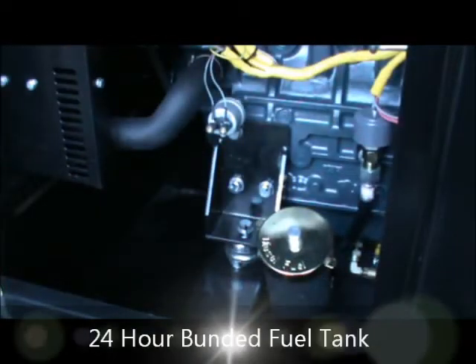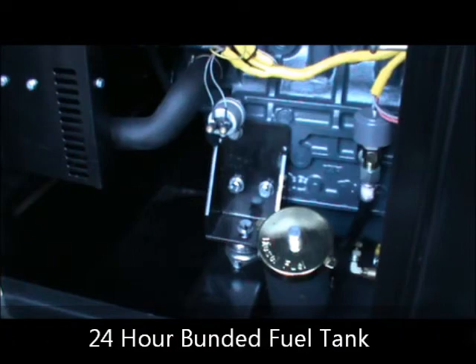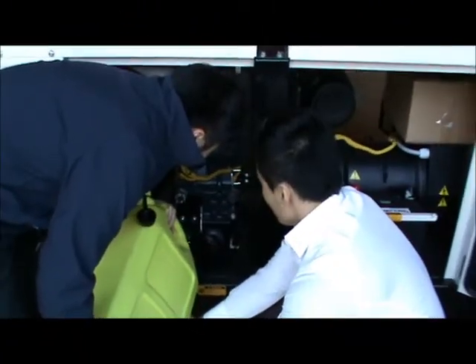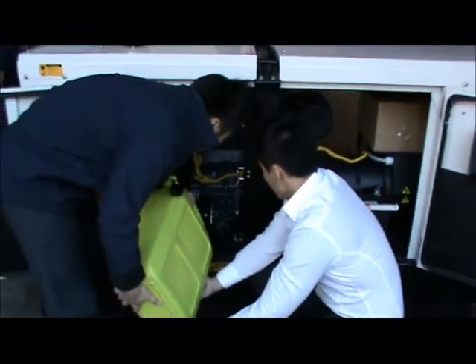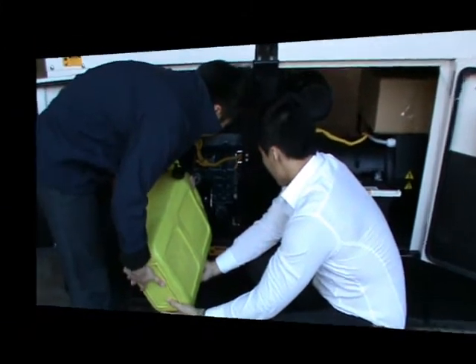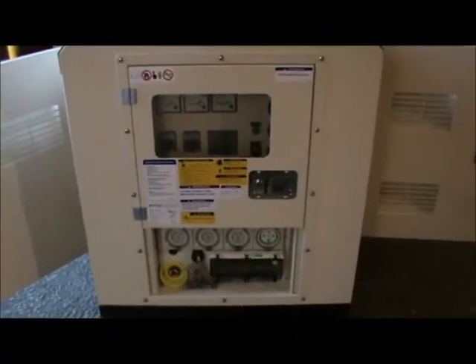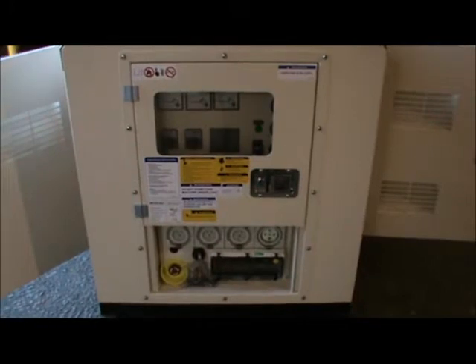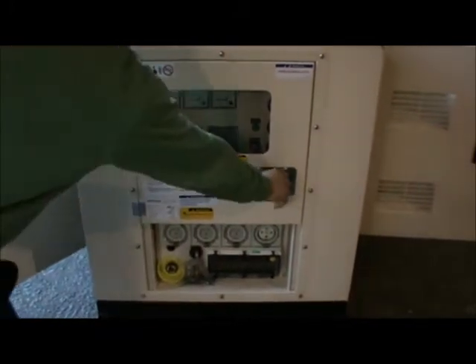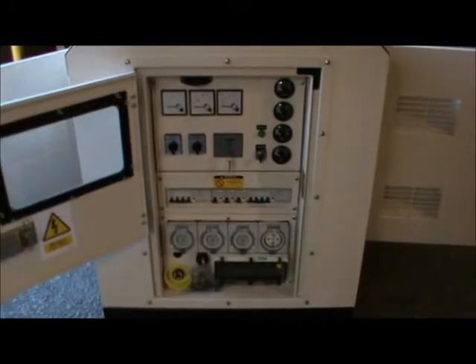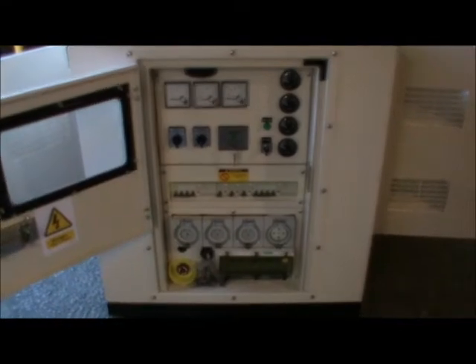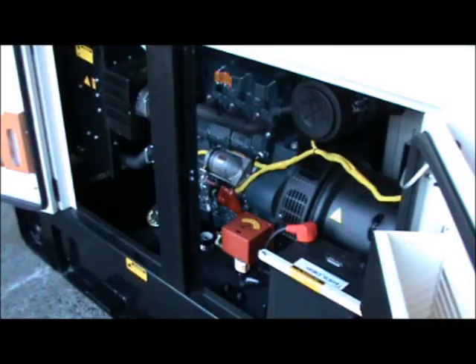The machine is also characterized by the 24-hour fuel tank for all 300 kVA sets and below, with 110% capacity. All 30 kVA and under sets use the Deep Sea 702 controller, whilst all sets over 30 kVA use the Deep Sea 7320 controller. A 4-pole circuit breaker, a battery isolator and charger, central lifting point, forklift slots and tie-down points.